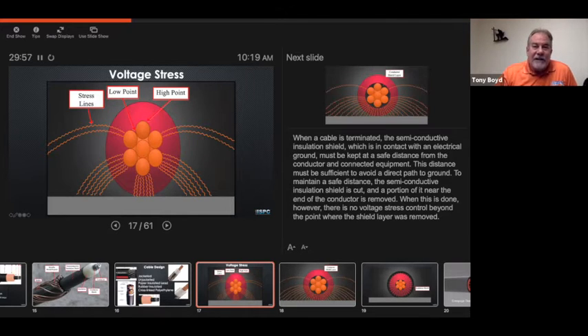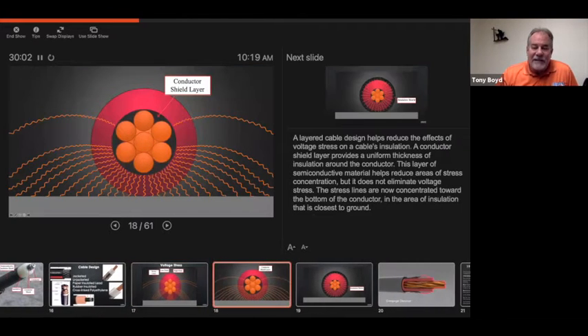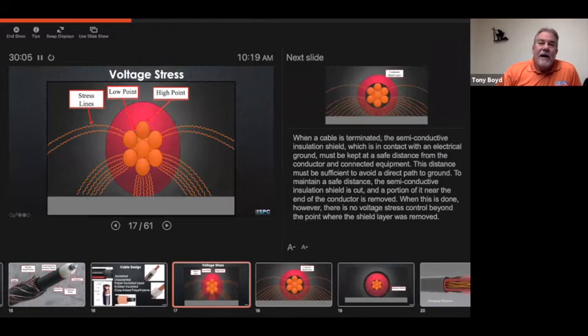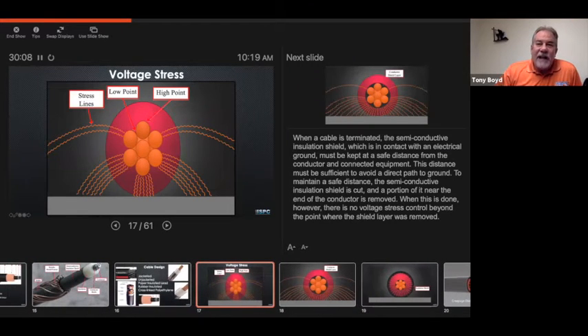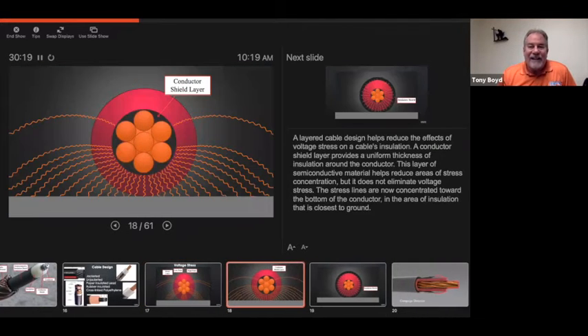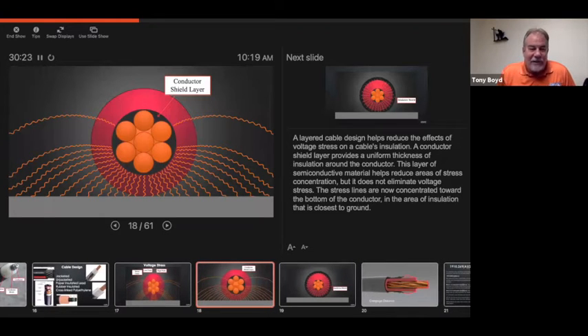So the semiconductor that goes around the conductor is actually lessening. All right, don't click this time. It's actually lessening these low points and high points, so that the stress is actually going through the insulation evenly. Now, someone may ask, is there any leakage? And the answer is yes, there is. So there's that conductor shield layer, which tells us that it's evenly bringing those stress lines out of the insulation.